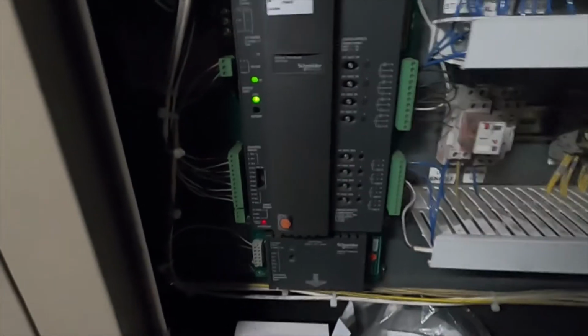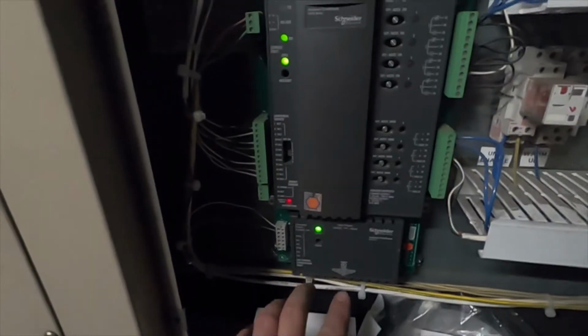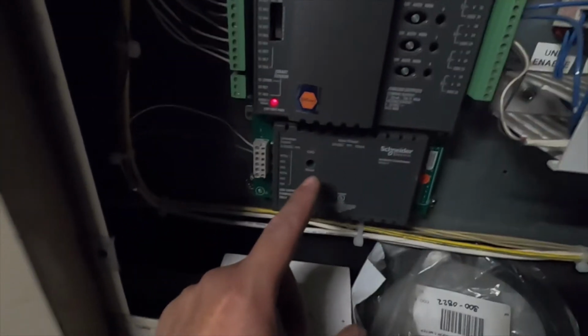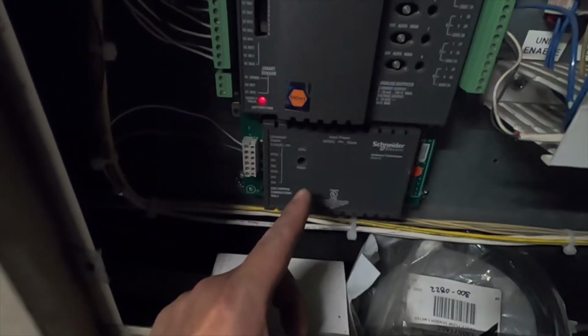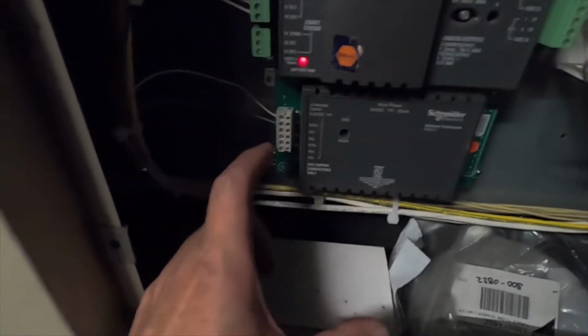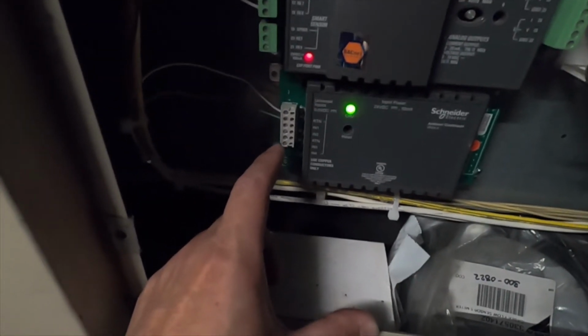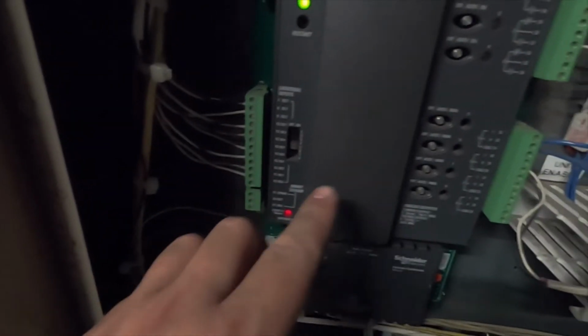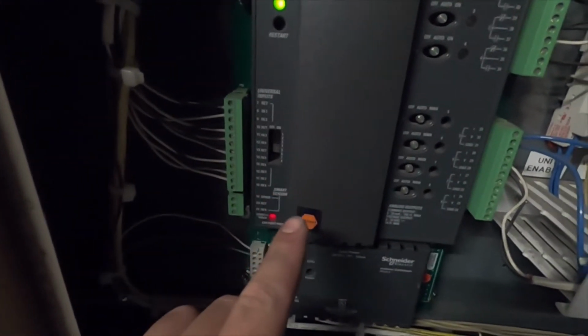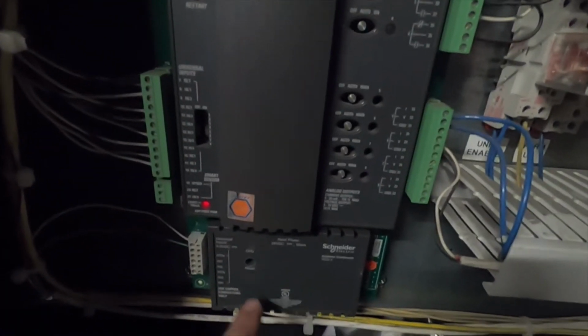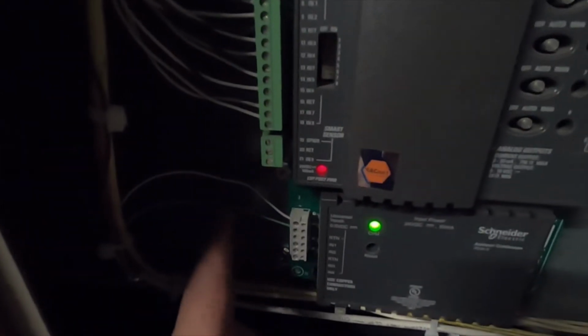What we had to do here is tack on an expansion module to give us additional inputs. All the inputs are used up on this controller, so we had to add the expansion to give us the extra inputs needed to add the 2 sensors.